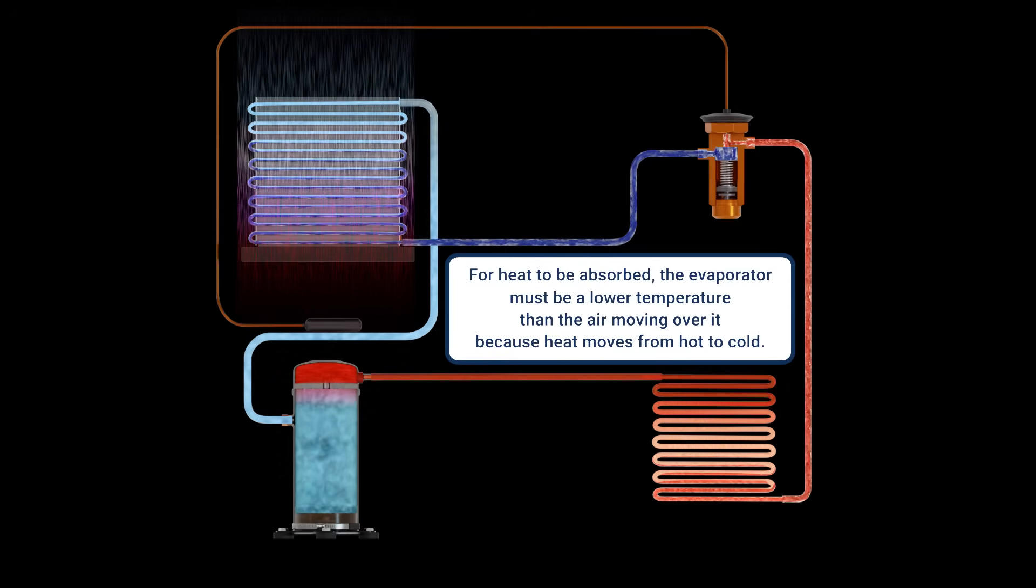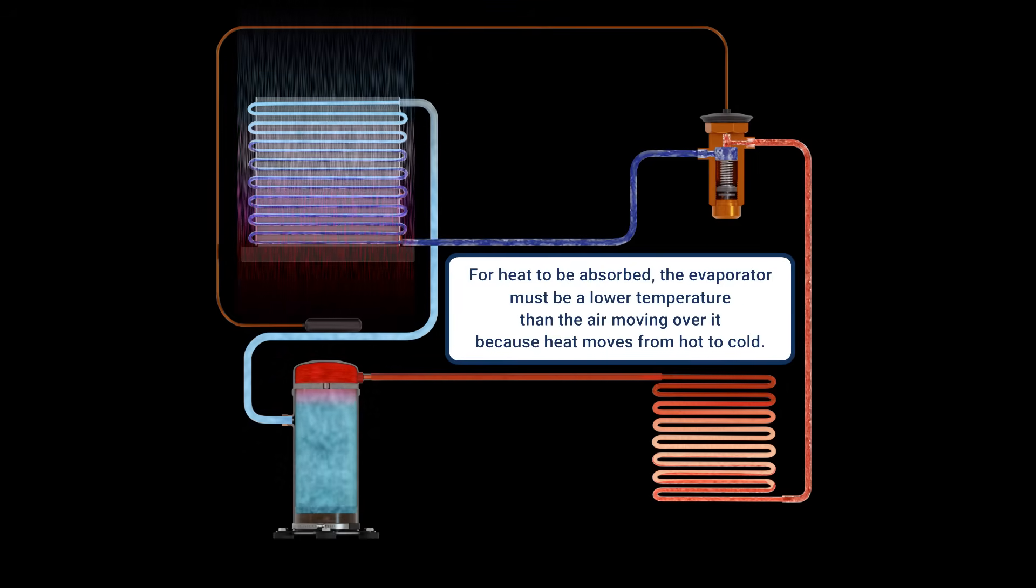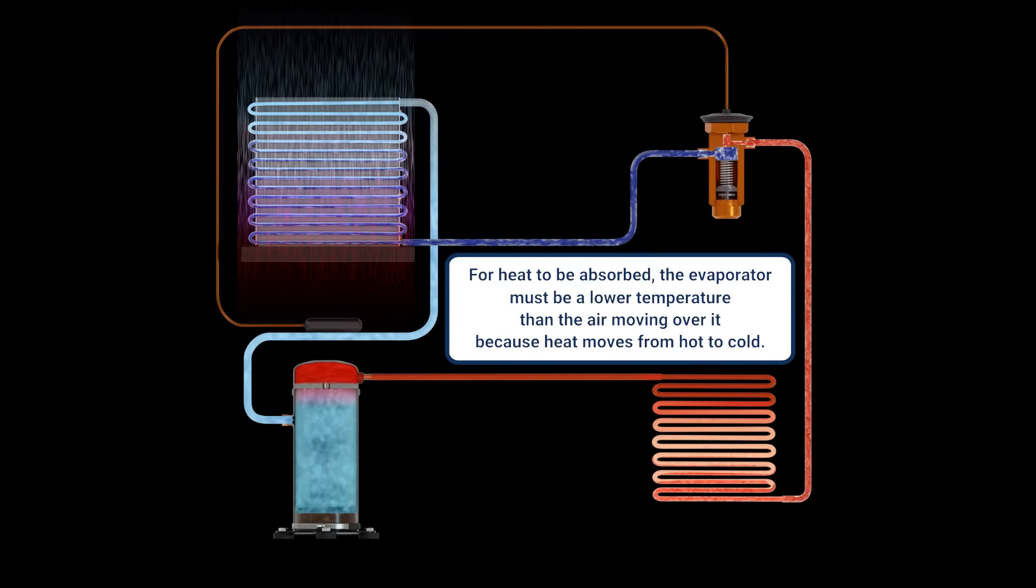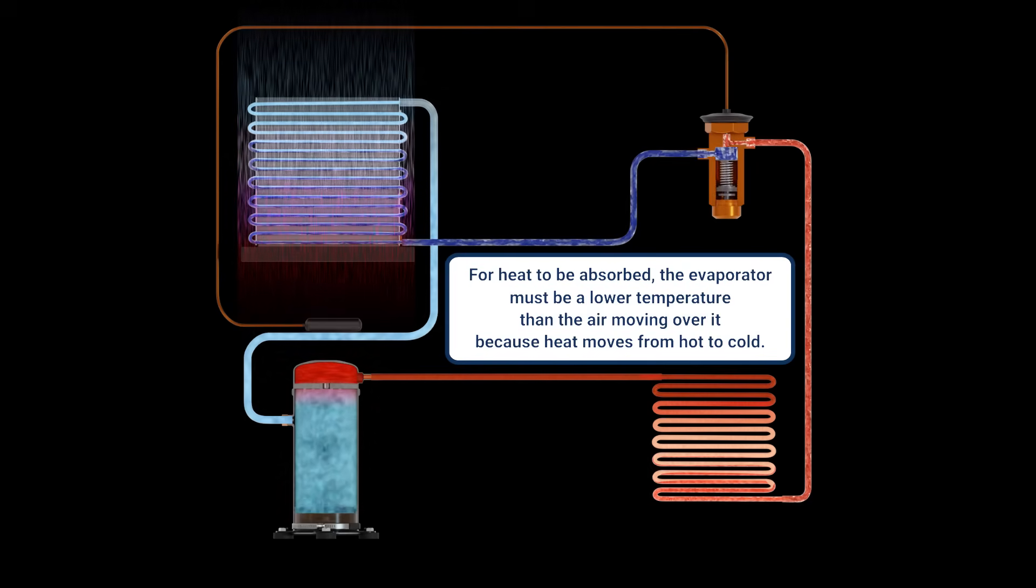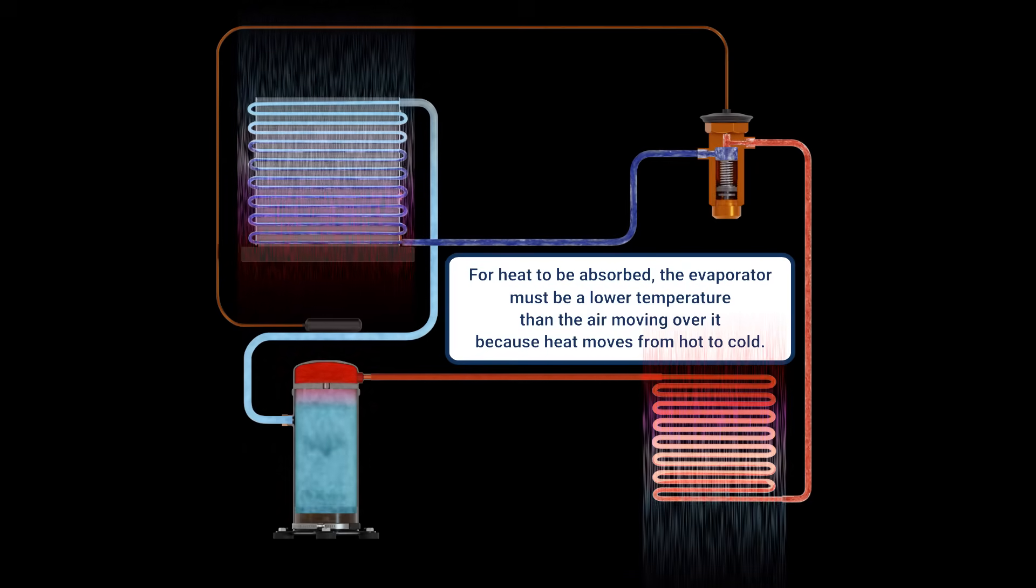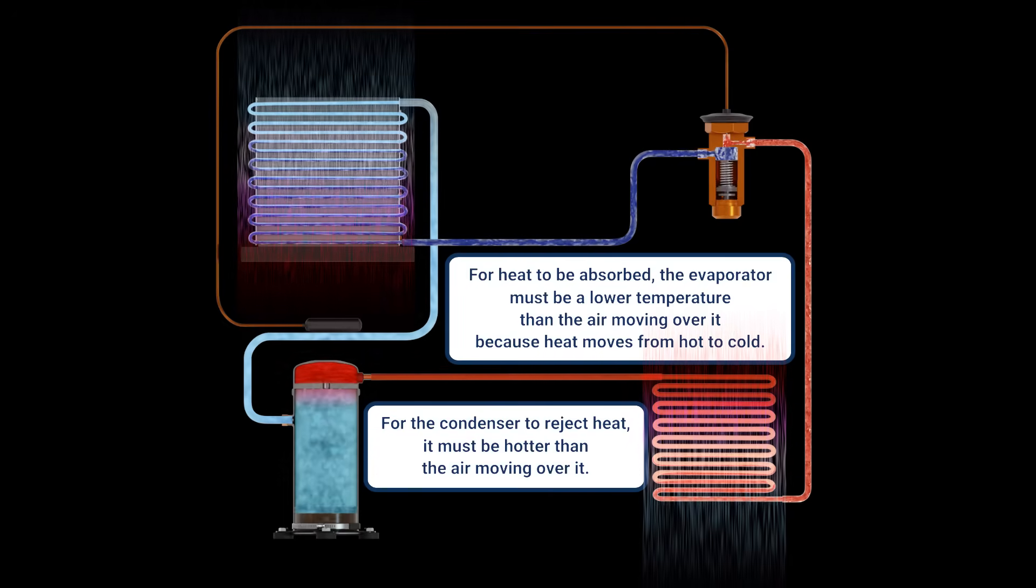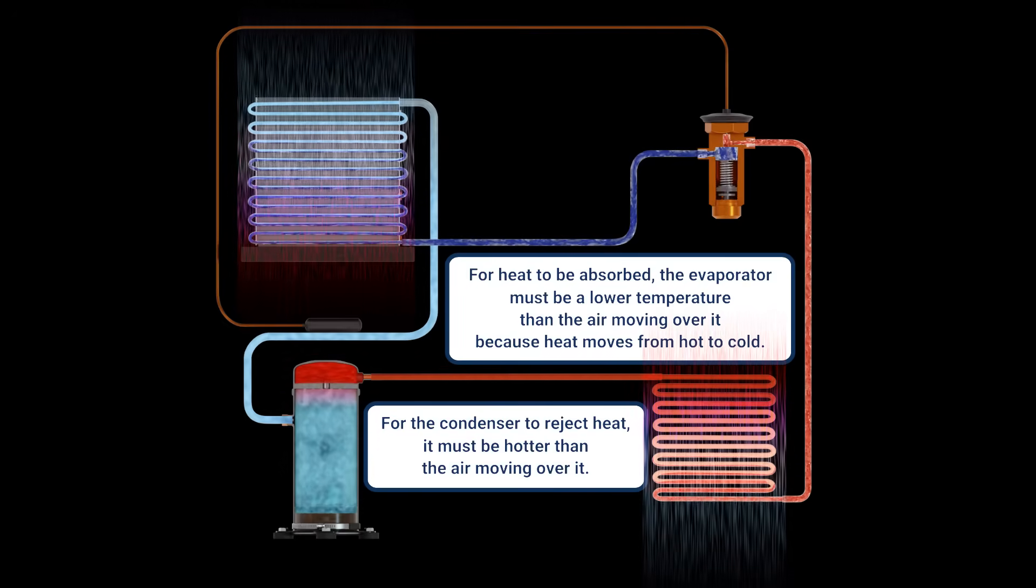Remember, for heat to be absorbed, the evaporator must be a lower temperature than the air moving over it, because heat moves from hot to cold. For the condenser to reject heat, it must be hotter than the air moving over it.